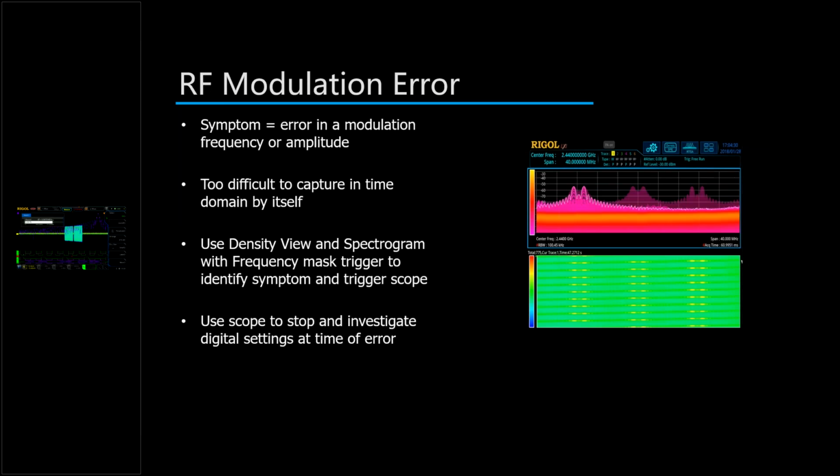All right, let's look at the next kind of problem we have. So this one is really more about modulation, right? So having a subtle problem in our frequency, as I reset the spectrum analyzer here for us. There we go. So being able to look at problems in frequency here and then capture them and investigate them in different ways.